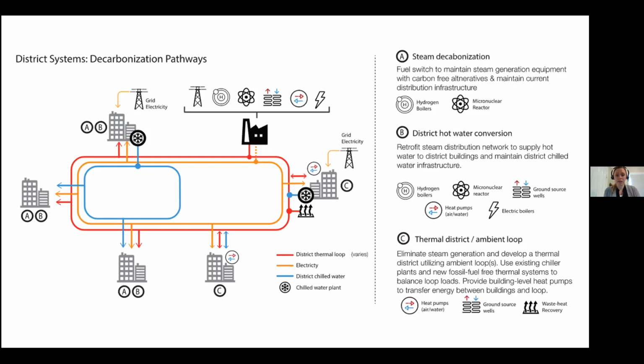Many systems at a campus level have been looking at converting those district steam systems into hydronic or water-based networks, and there are challenges with that transition from steam to hot water, even if it is medium or low temperature hot water. The benefit is that it's easier to generate lower temperature water with a wider array of kit of parts.